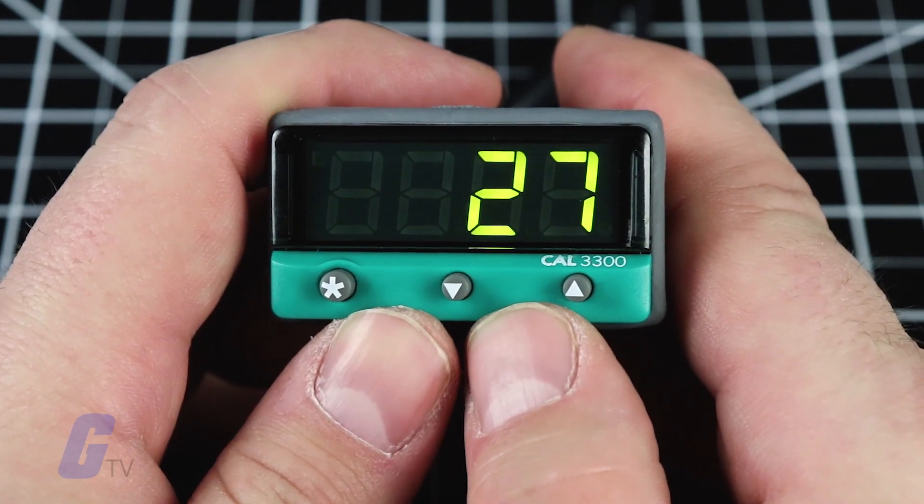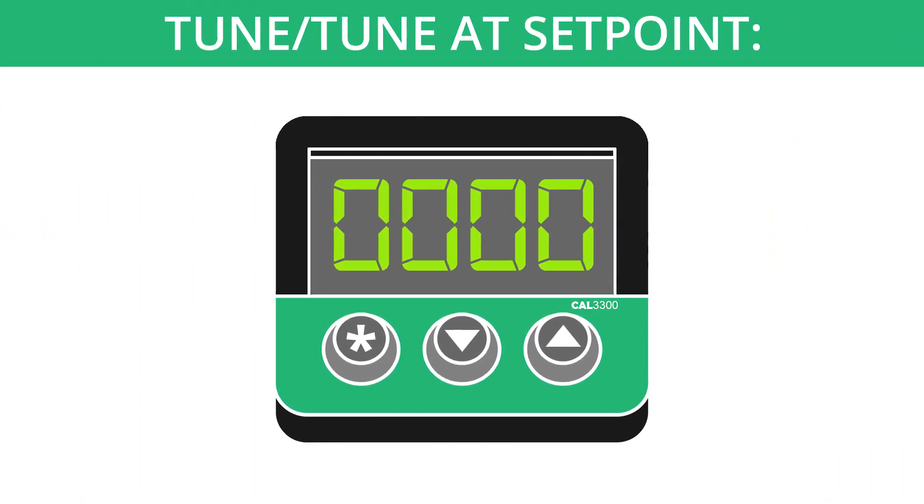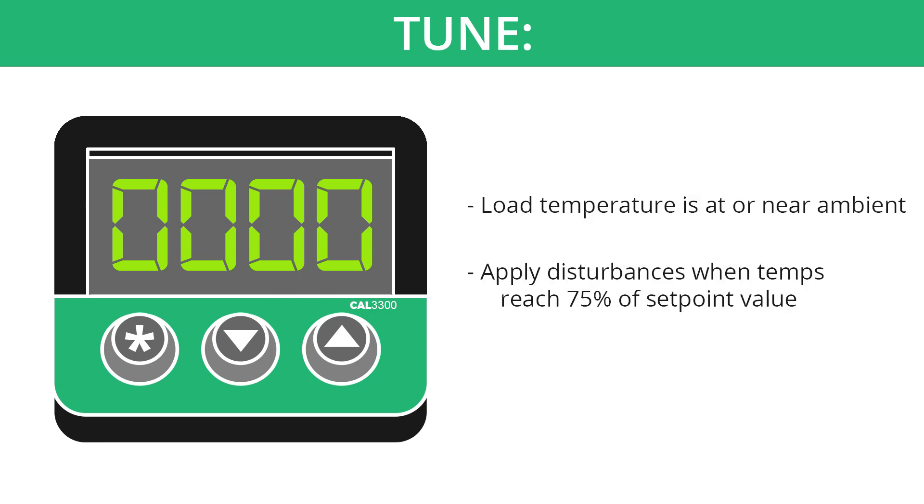However, you may wish to further tune the unit for process control. This is easy to do with the auto-tune feature. You will have two options: tune at setpoint and tune. The tune program should be used when the load temperature is at or near ambient. The procedure will apply disturbances when the temperature reaches 75% of the setpoint value, causing overshoot which is monitored in order to adjust the CAL overshoot inhibit feature.